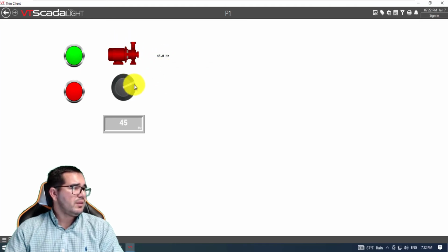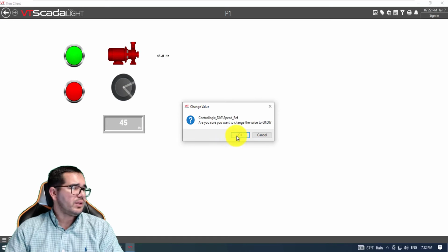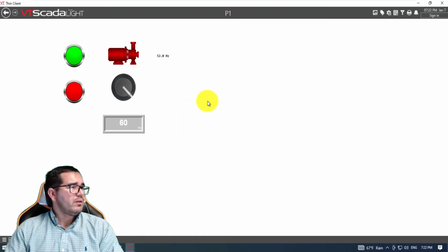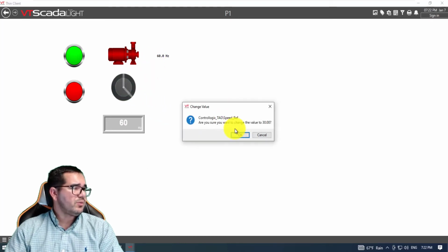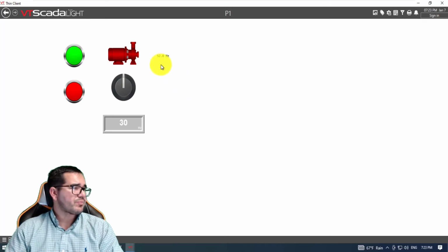Let me go to 60 hertz right now. Okay, 60 hertz and we are done. Let me put it on 30 hertz right now. And let's see, we can see here the speed going down. And I'm going to stop the pump here.